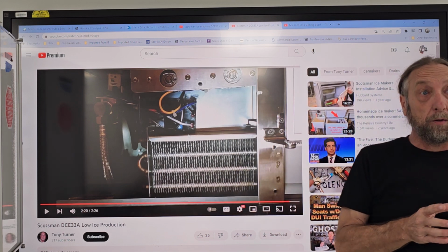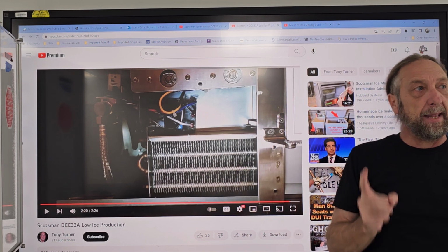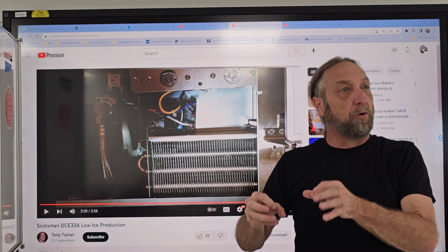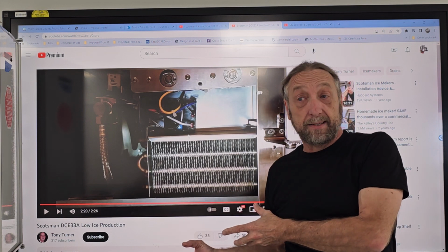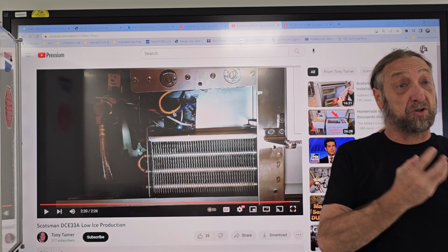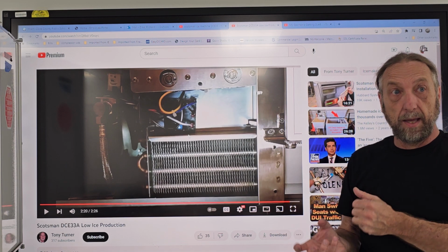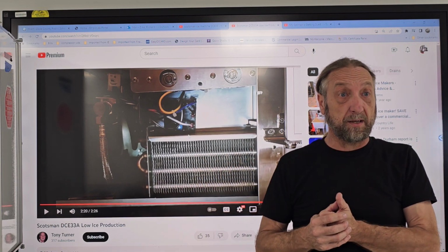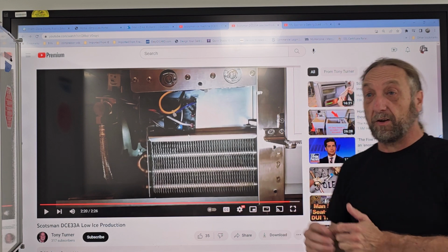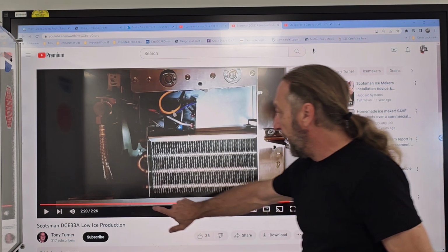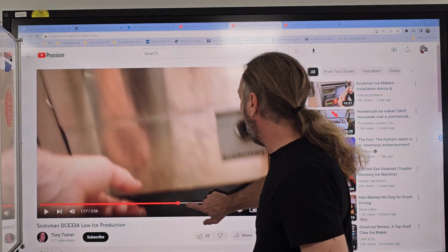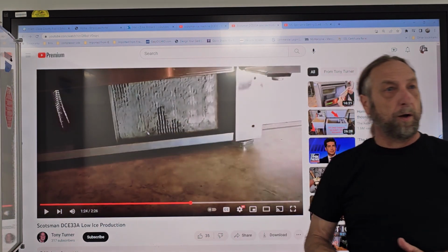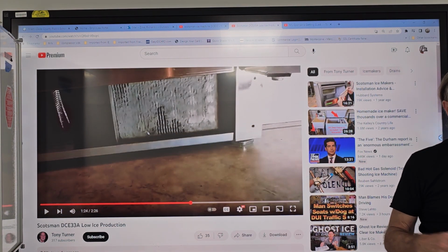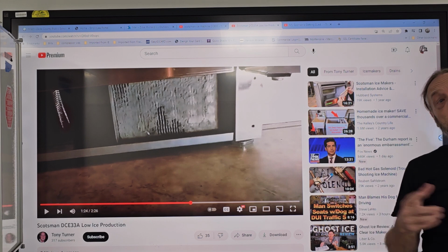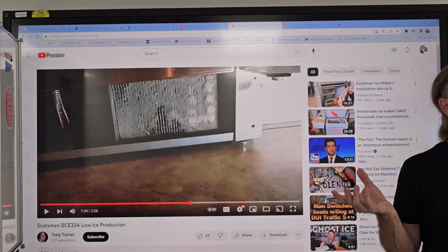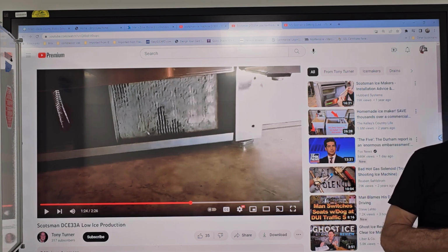They have a little bit of oil on the bottom of them. And that oil may turn to vapor in the excessive heat and flow through your system and cause a problem with your refrigerant system. So you tell the customer, listen, you see how dirty this coil was? If we go back to his dirty coil, you see how dirty that coil was? Yeah, you might say, oh, well, I'm gonna have to pay for a cleaning every year. I don't know if I'll spend $120, $150 on the cleaning.